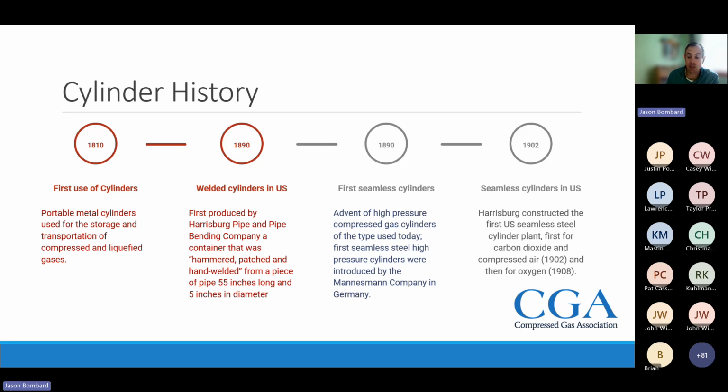And actually, a good number of those cylinders are still in circulation in the country. I know I've personally seen a couple that came in for requalification from 1910, 1911. They were still perfectly fine cylinders, and they went right back out for continued use.